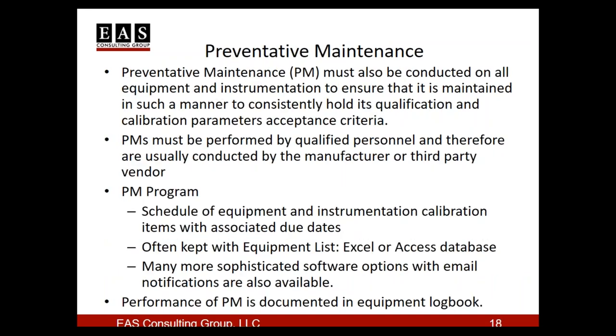Once we've done all this work to qualify and calibrate it, we have to maintain the equipment. This is typically called a PM system or PM program, and it's conducted for all equipment and instrumentation to verify that we're going to be able to hold the qualification and calibration. This is often done for more sophisticated equipment, often by third-party vendors that will come in and do PMs on all your HPLCs, for example, but you can do it in-house if you have appropriately trained personnel.